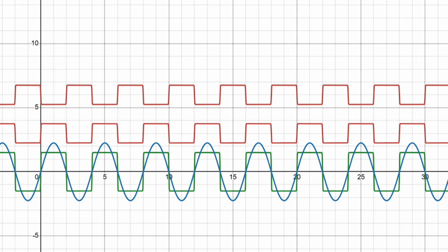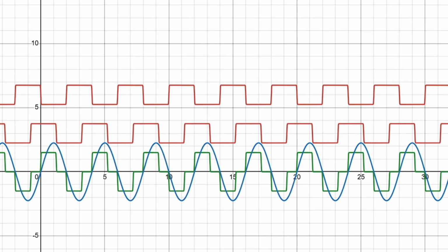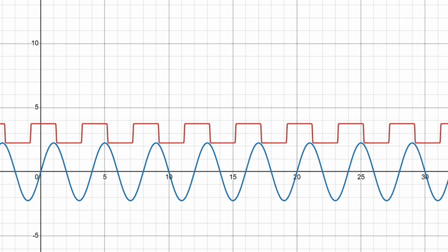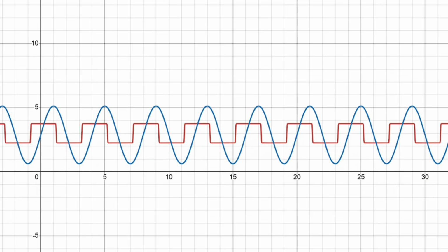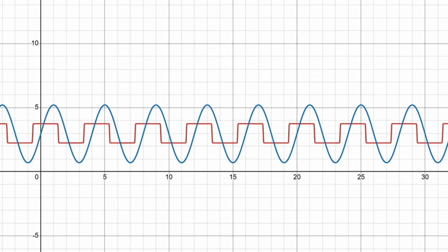The big downside of phase shifting is that now one of the half bridges is switching out of phase with the primary current. This leads to hard switching, which happens when current is still flowing through the switch while it changes states. This is bad for transistors, causing extra heating and shortening their lifespan. Even with this downside, I still like phase shifting better because it's more elegant and cuts down on power electronics, which are typically pretty expensive.